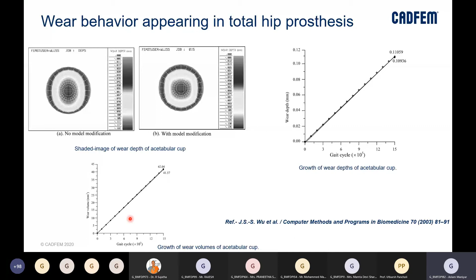And you can see certain loading stages, with forces acting onto the hip joint in one gait cycle. You can see the maximum force going up to 350 Newton. So you can apply all these loadings and do a wear modeling analysis to get the wear depth with respect to material removal or gait cycles, and you can also see the wear volume. So this kind of analysis is also possible.